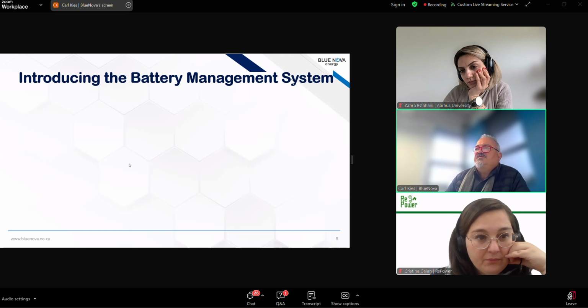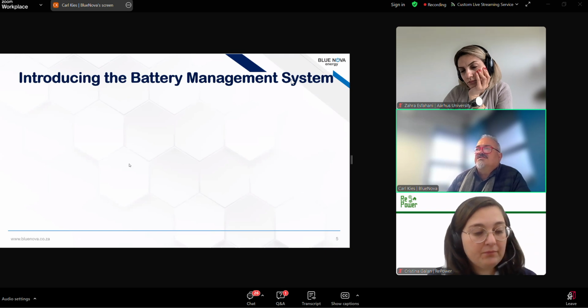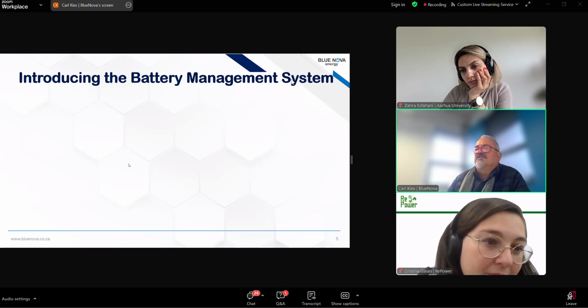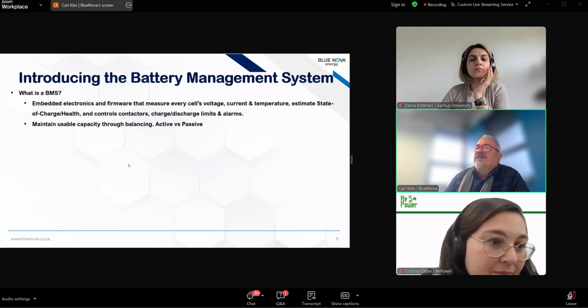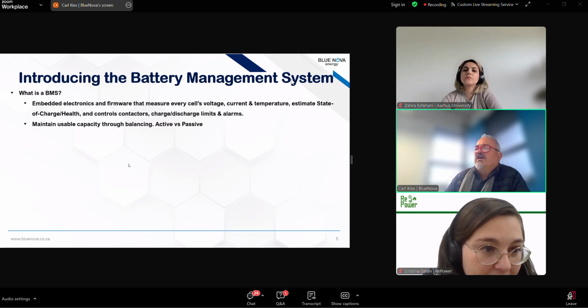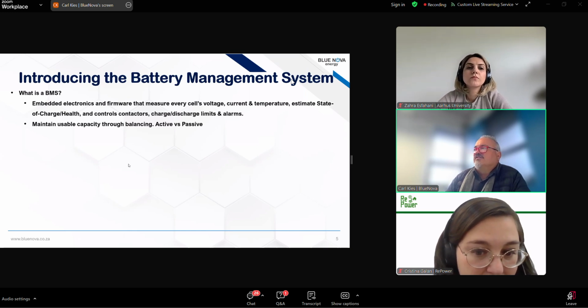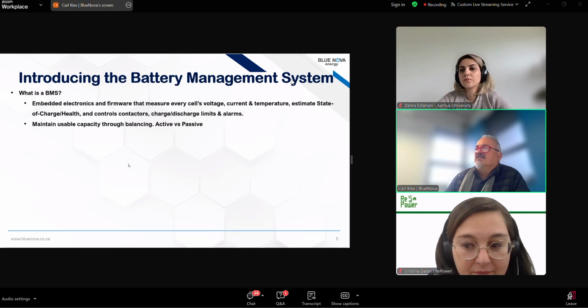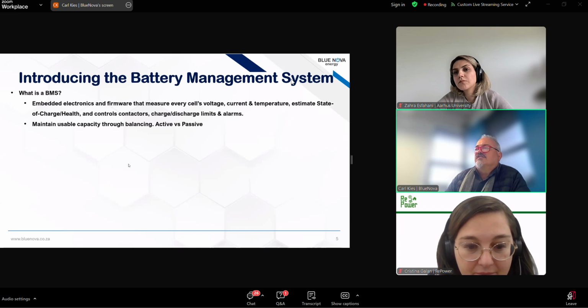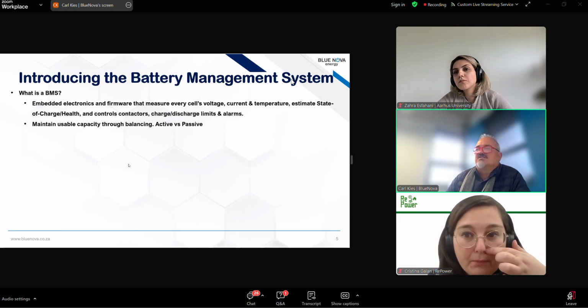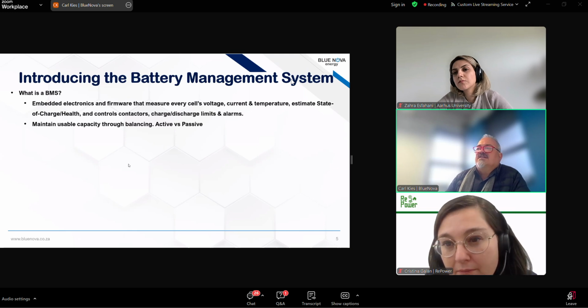So we've spoken briefly about the battery management system. For those new to it, here's a quick overview: it's basically electronics and firmware in the battery that measures the voltage of every cell, looks at the current and temperatures, and estimates state of charge and state of health. It controls contactors and charge/discharge limits, sets alarms if the battery is outside safe operating areas, and maintains usable capacity through balancing, which can be active or passive.